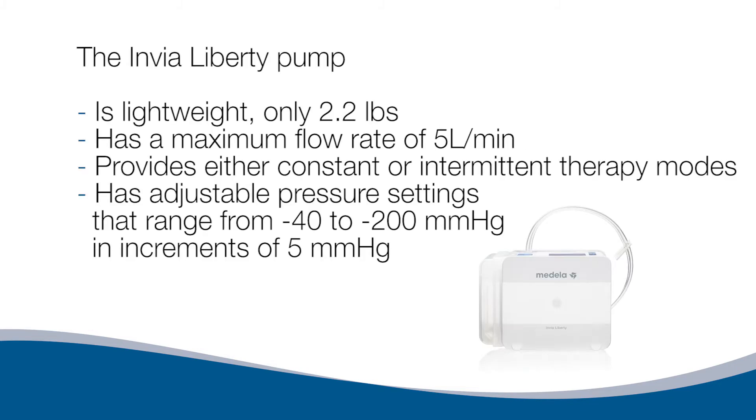The Invia Liberty pump is lightweight, only 2.2 pounds, has a max flow rate of 5 liters per minute, and provides either constant or intermittent therapy modes. It has adjustable pressure settings ranging from negative 40 to negative 200 millimeters of mercury, in increments of 5 millimeters of mercury.